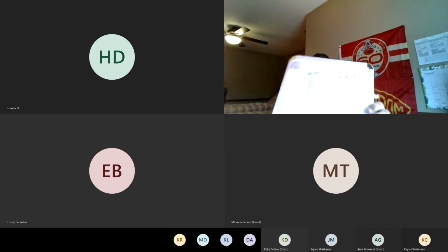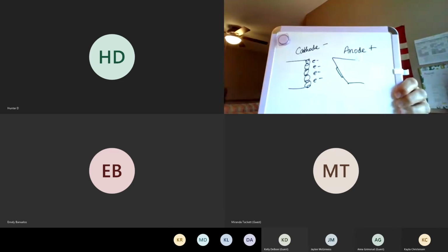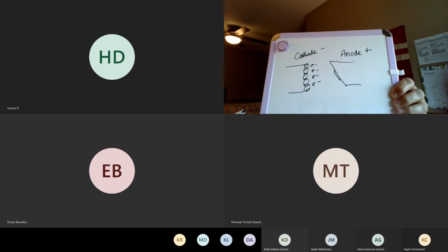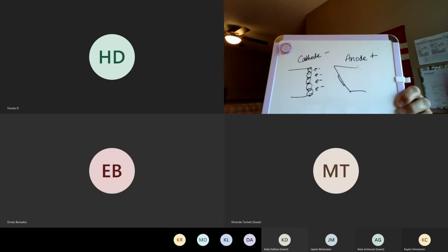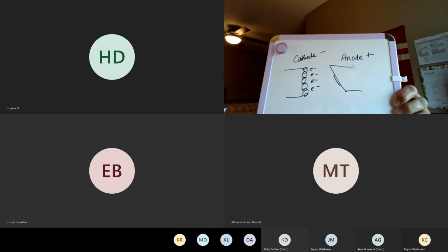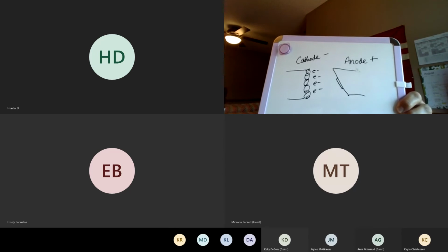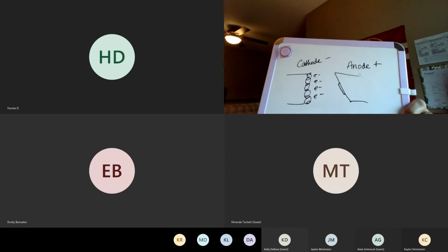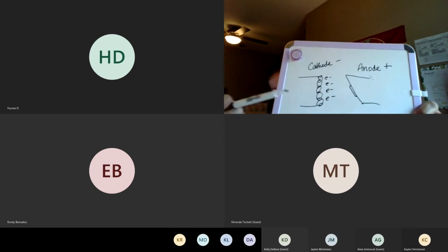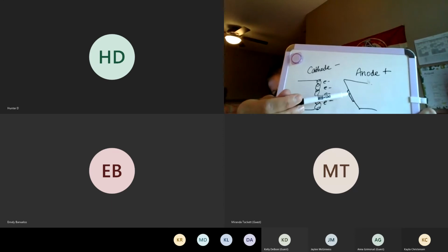All right, so electrons will build up around the negative cathode like this. And then when enough of those build up through thermionic emission, with the high voltage circuit we will apply kVp between 65,000 to probably more like around 70,000 in our dental units. That will provide enough energy to give them the speed or penetrability to drive across to this anode target right here. Okay, at that anode target is where they become X-ray photons.